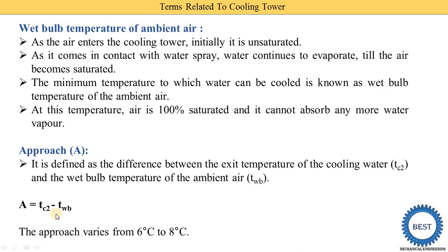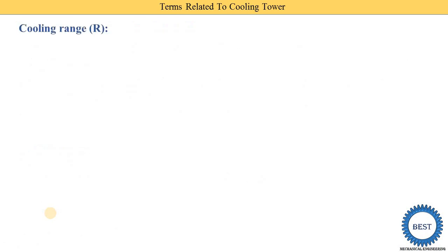For example, suppose the wet bulb temperature of the atmosphere air is 30 degrees. Then we are able to achieve a cooling water temperature of 36 to 38 degrees. If the wet bulb temperature of the atmosphere air is 35 degrees, then the minimum temperature we can achieve for the cooling water is 41 to 43 degrees.